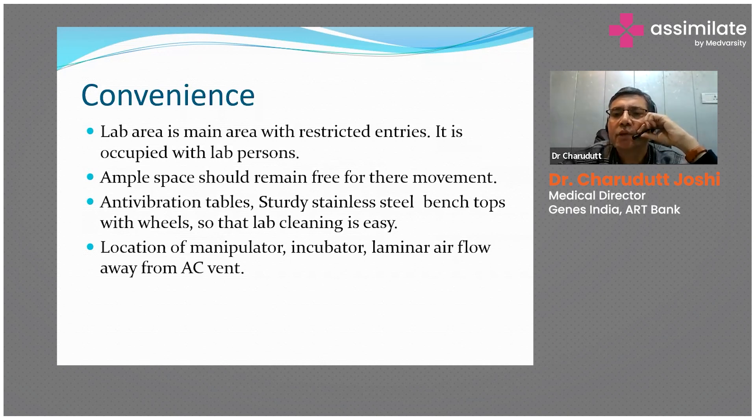Anti-vibration tables and sturdy stainless steel bench tops with wheels are needed so that lab cleaning is easy. The ICSI machine — intracytoplasmic sperm injection — must be placed on a totally vibration-free platform. The needle used to inject sperm inside the egg is 100 times smaller than a single hair, so even a slight disturbance causes vibration that can damage the egg. Stainless steel tables with movable wheels are very helpful for cleaning the floor — you can move them, clean, and return them to the original location.